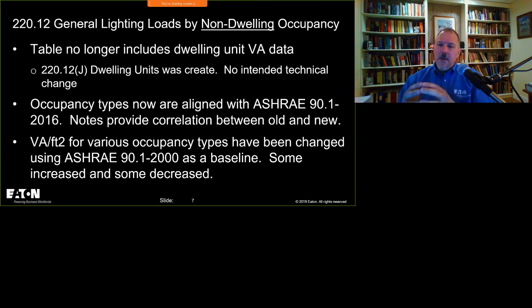our equipment. I mean, if you think about it, we've been doing load calculations for quite some time, and the concern that was raised was that we do these load calculations, and yes, do we have transformers that are probably bigger than what they need to be? Sure. We have conductors that are probably bigger than what they need to be. Yes, we probably do. But as we start lowering the rating, closing the gap between what's actually being used and what the rating is, there's probably going to be more heat generated in all of this equipment, and how much of the capacity that you're leveraging, what that impact is on the longevity of the equipment is really unknown, because we probably have been sizing these things differently. We've been in this practice of a larger margin for quite some time, and that usually covers a lot of mistakes, right?